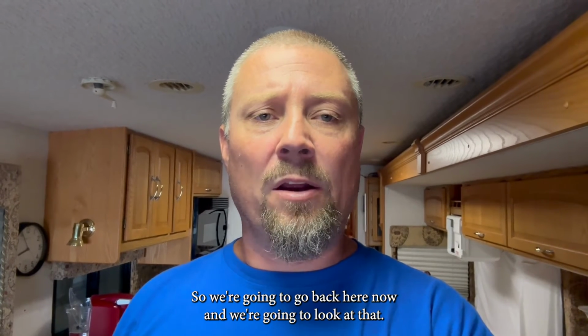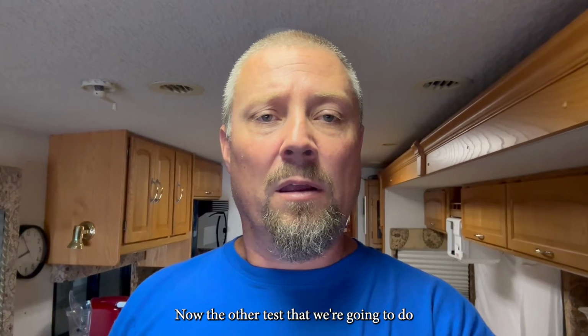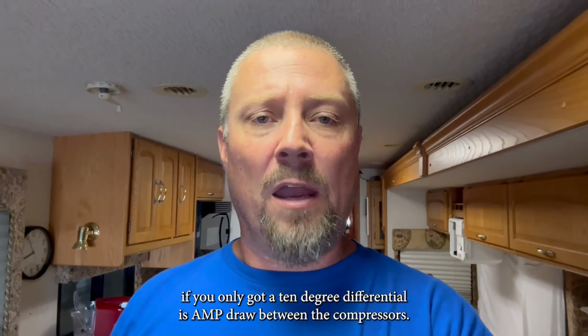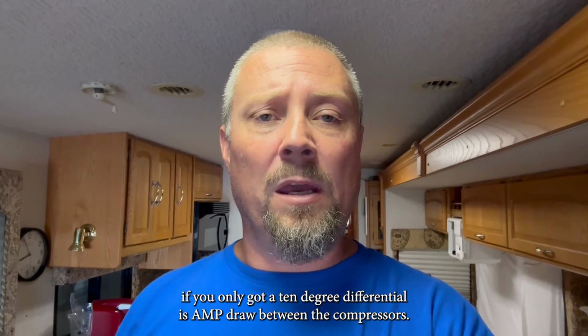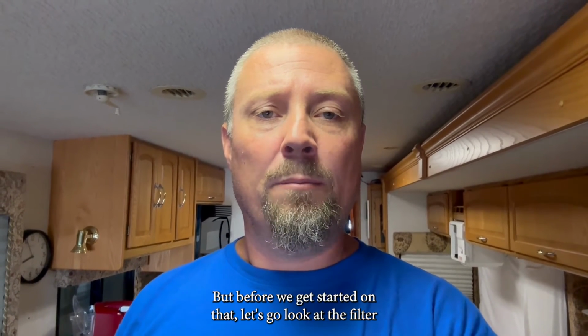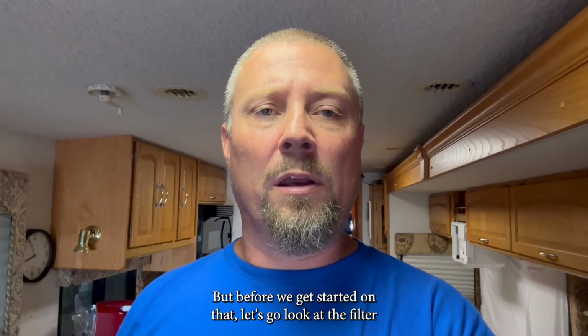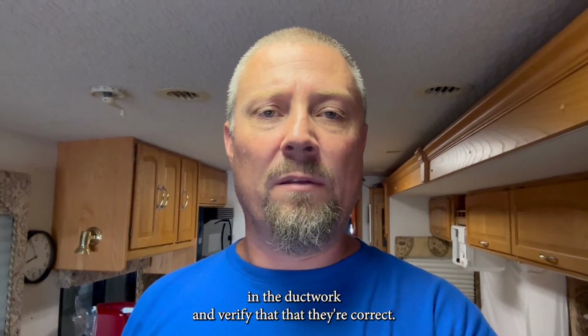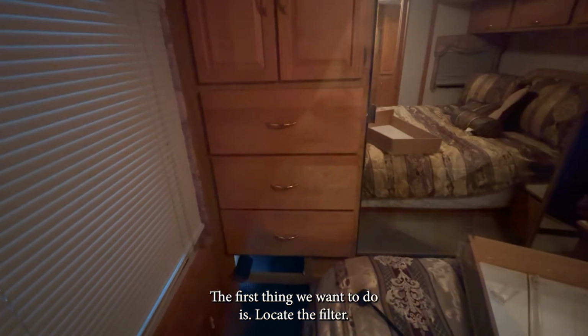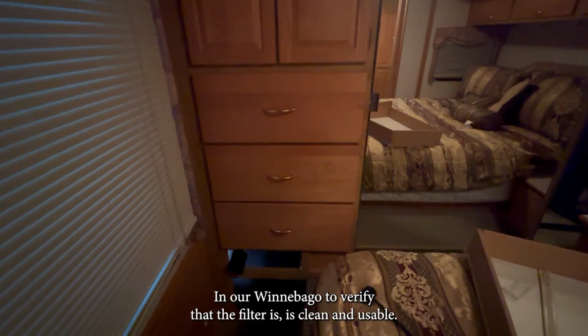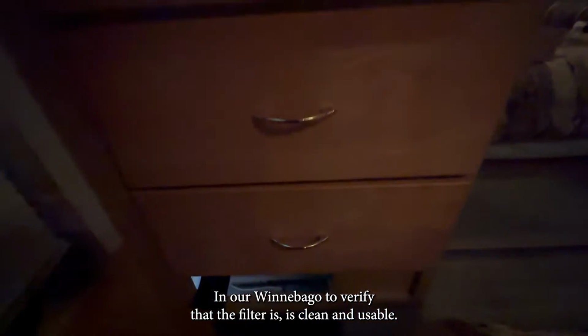So we're going to go back here now and look at that. Now, the other test that we're going to do, if you only get a 10-degree differential, is amp draw between the compressors. But before we get started on that, let's go look at the filter and the ductwork and verify that they're correct. First thing we want to do is locate the filter in our Winnebago to verify that the filter is clean and usable.